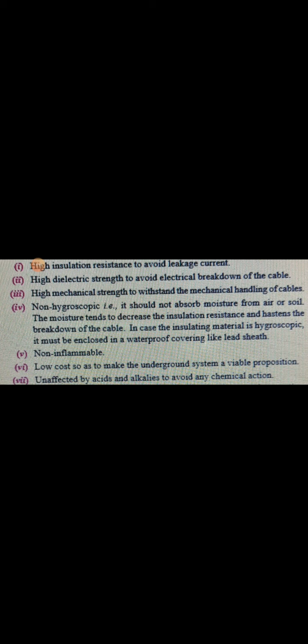Then the next property is that the insulating material should offer high mechanical strength to withstand the mechanical handling of cable. Next, it should be non-hygroscopic. Similarly, it should be non-inflammable. Then the next property is low cost. The cost of the insulating material used in underground cable should be low, so as to make the underground system economical. And the insulation should be unaffected by acids and alkalis to avoid any kind of chemical reaction. So these are the main properties of insulating material used in underground cable.